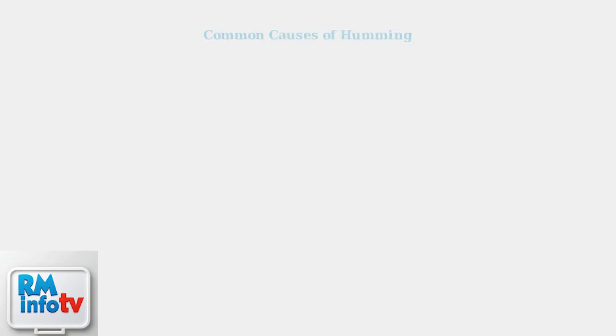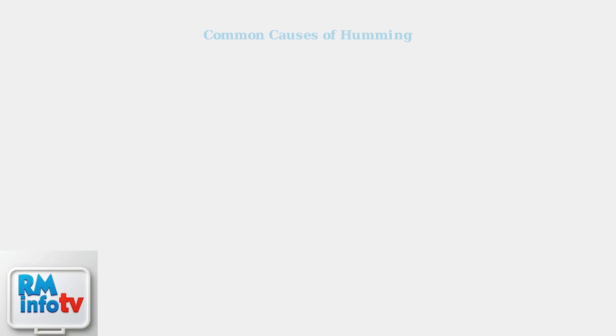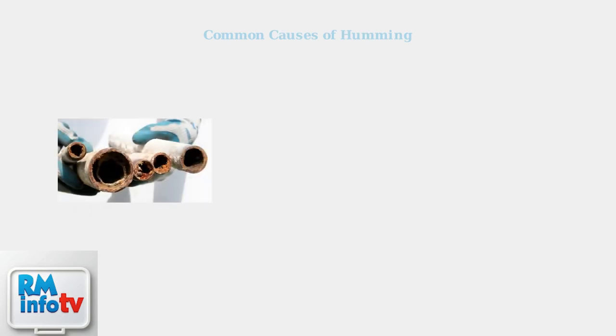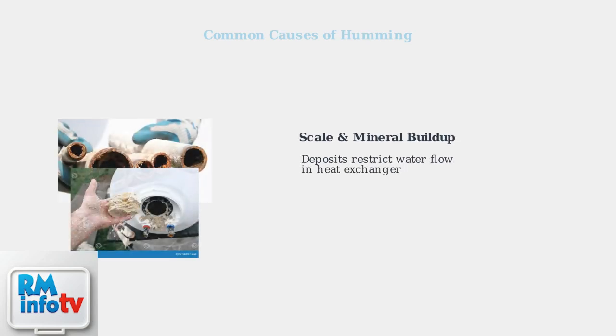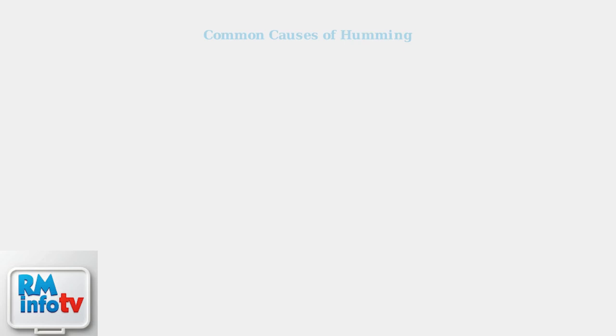The first common cause is loose components. Over time, vibrations can loosen screws, panels, and fittings throughout your water heater, creating humming or buzzing sounds. Scale and mineral buildup is another major cause. These deposits accumulate in the heat exchanger, especially in hard water areas, restricting water flow and causing humming sounds as water struggles to pass through.